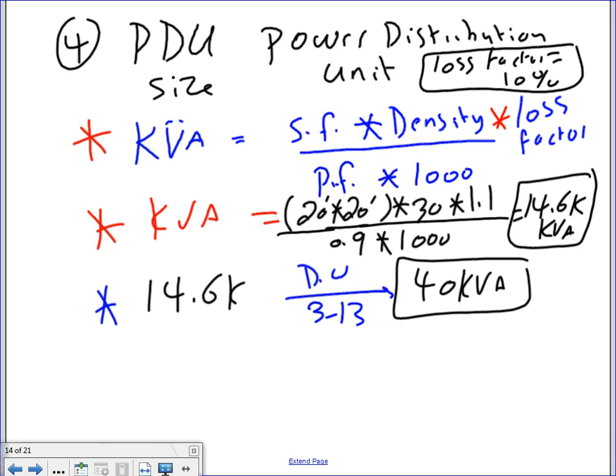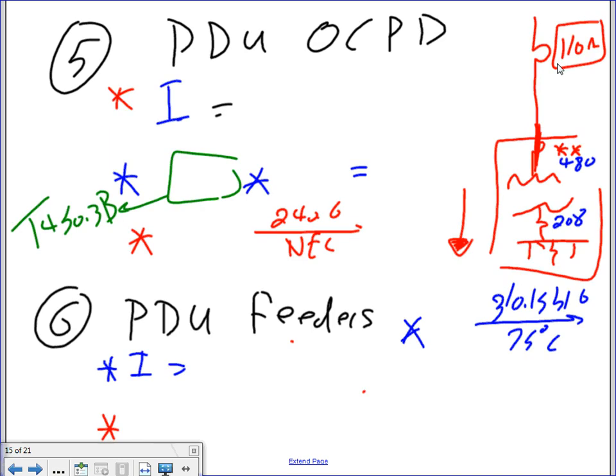Okay, then you can imagine the calculation will be very similar, right? We got that one. Then if you go to number 5, you need to take the same thing, the PDU 40 kVA divided by, on the primary side, 1.73 times 480, and that will give me 48 amps.